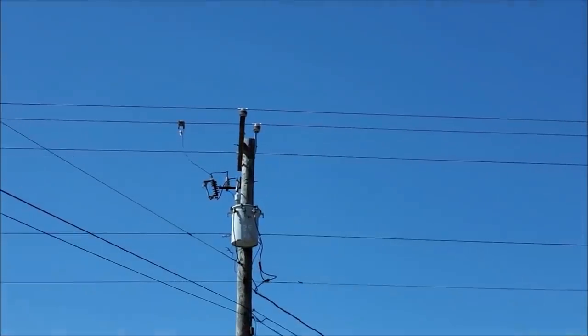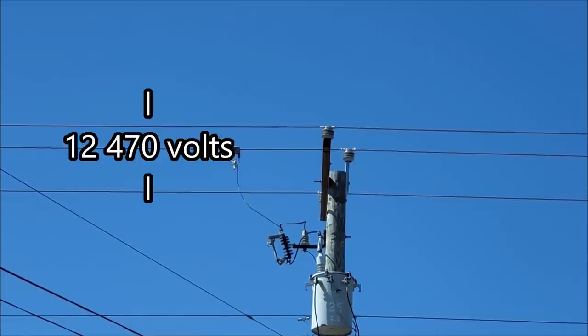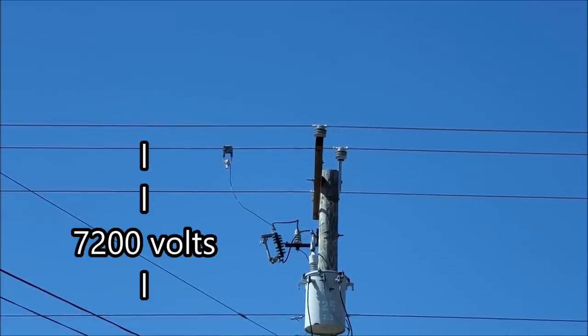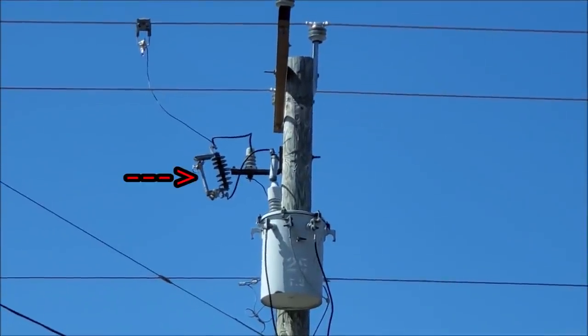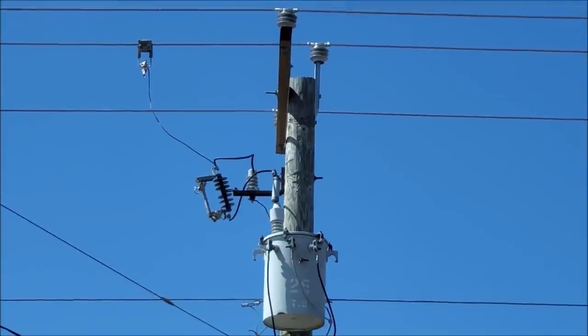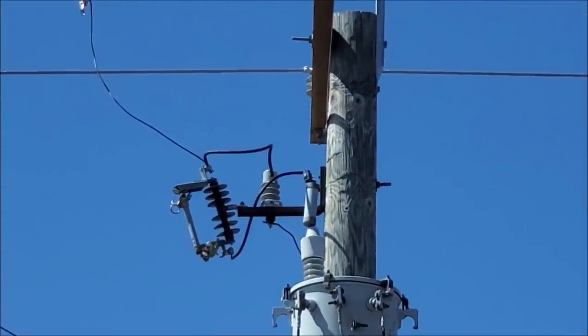This is all stuff they figured out a long time ago — technology hasn't changed much, it's a fairly analog setup. The bigger the fuse is rated for, the bigger the piece of wire inside, and the more heat it's going to take to melt that fuse link. You coordinate these fuse links in the lines so that they get smaller and smaller, so it takes less heat — less current — to trip them. When everything is coordinated properly, you have a system that is more reliable, able to isolate faults according to where the current spikes are. Then why is it that sometimes a transformer blows up? Why doesn't the fuse blow? Generally speaking, when you hear someone say the transformer blew up, it didn't — it's just the fuse. When a fuse blows, it's loud and it can be pretty aggressive. This is just a single-phase transformer where you can see the high-voltage lead taps onto the main phase. The phases up top are 12,470 volts phase-to-phase, approximately 7,200 volts phase-to-neutral or phase-to-ground. It comes down into our cutout; this particular transformer is a 25 kVA, so we have that cutout fused at 6 amps.